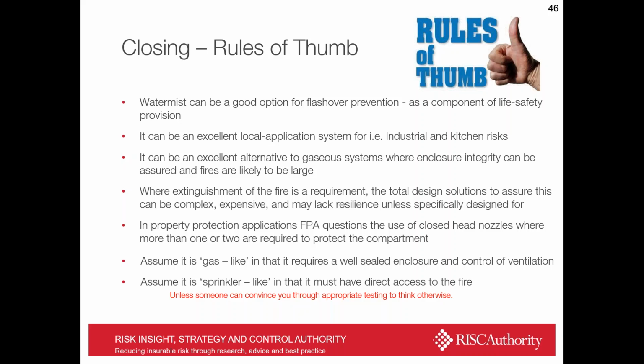And finally, when asked whether it's sprinkler-like or gas-like, to be on the safe side, assume it's gas-like in that it requires a well-sealed enclosure and control of ventilation, but also assume that it's sprinkler-like in that it must have direct access to the fire. Really, assume that where the water doesn't go, the fire won't go out, unless someone can convince you otherwise.